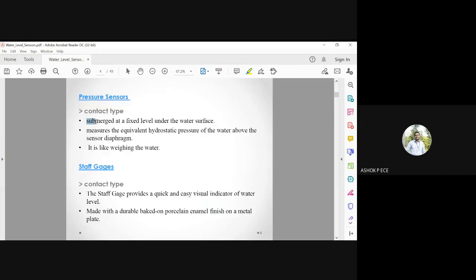The contact-type pressure sensor is submerged at a fixed level under the water surface. For example, if a tank must always be 50 percent full, the pressure sensor is fixed at that level. As the water level rises and touches the sensor, it measures the pressure created above it — similar to weighing the water. The water level is measured proportional to this pressure. This is a contact type because water physically touches the sensor.